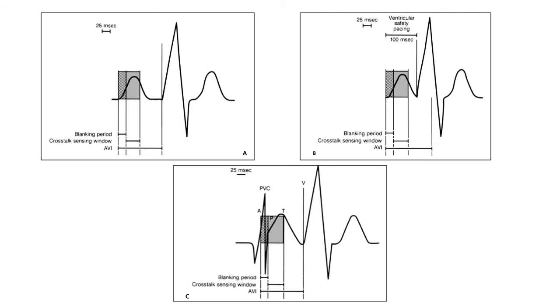So if an atrial pacing artifact is sensed by the ventricular sensing circuit, ventricular output inhibition should result. And this is called the crosstalk. To prevent the crosstalk, the leading edge of the atrial pacing artifact will be masked or blanked by making the ventricular sensing circuits absolutely refractory during the very early portion of the AV interval. The second part is the crosstalk interval, and if the ventricular sensing circuit senses any activity during this crosstalk sensing window, a ventricular pacing artifact will be delivered early, usually at 100-110 milliseconds after the atrial event, and this is known as the ventricular safety pacing.